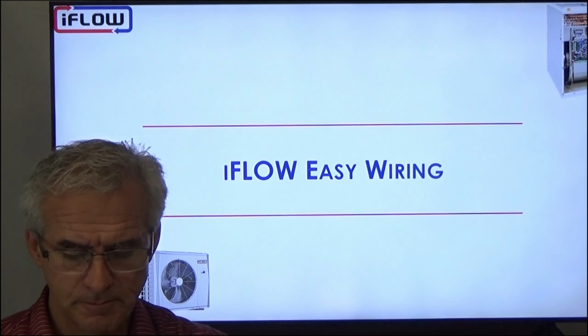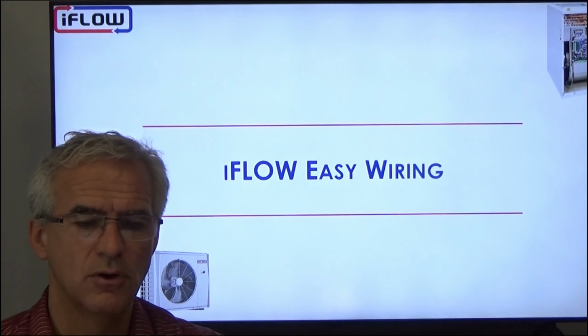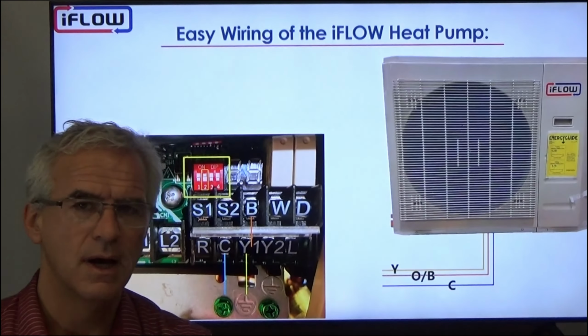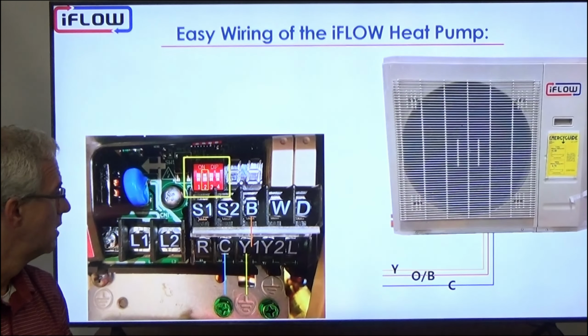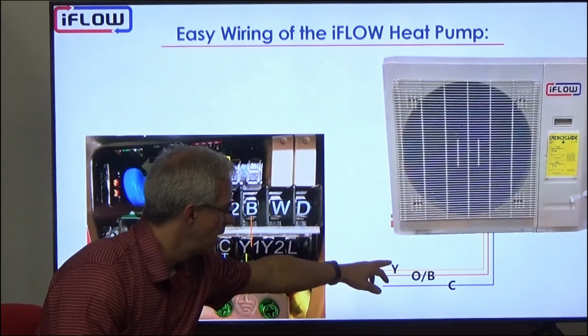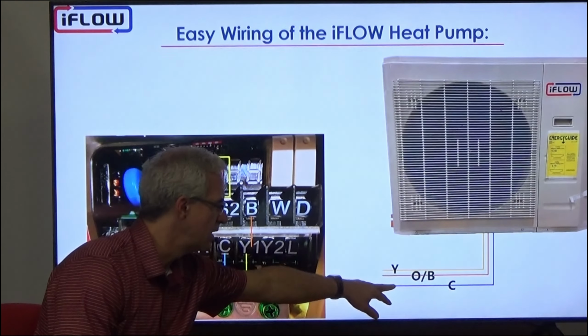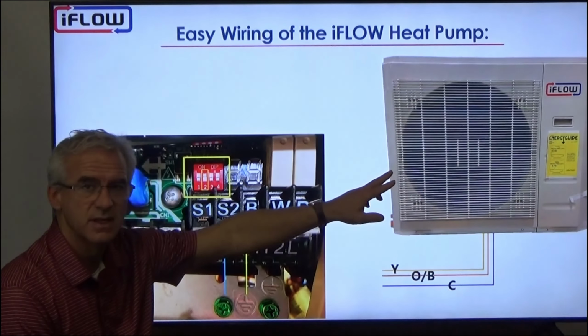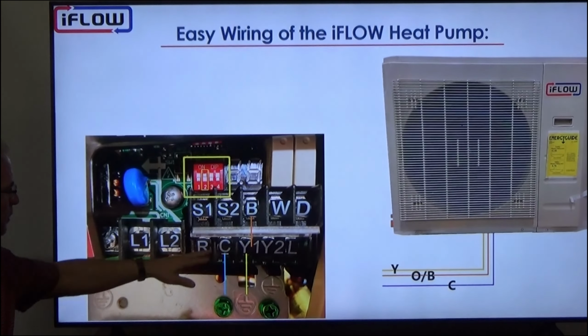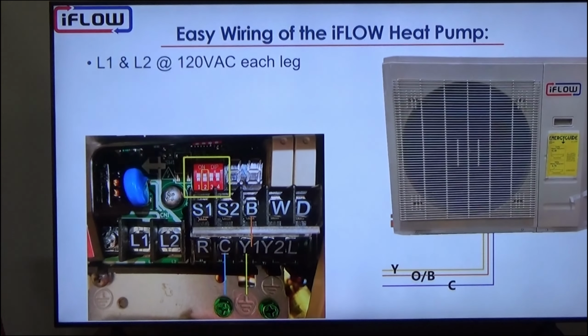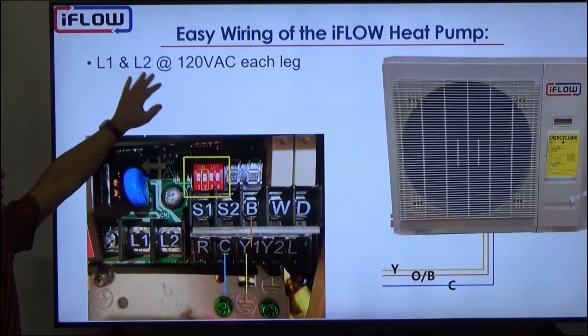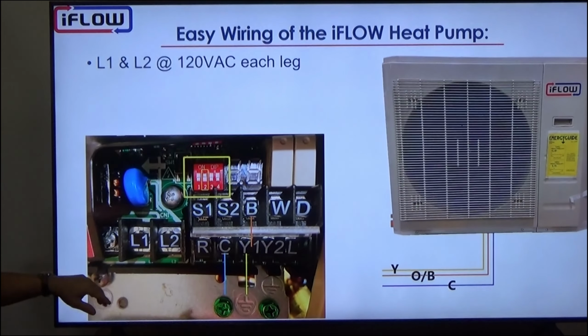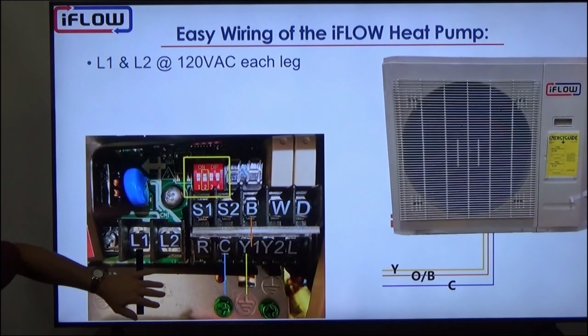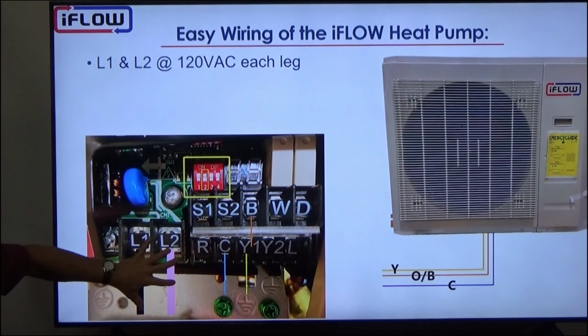In terms of wiring, the wiring to the iFLOW outdoor unit is very, very simple. We only require 3 wires. So we have a Y wire, an O or a B wire, and then a C wire. So 3 wires going out to the condenser unit. They connect simply to these contacts. So let's look at it. We have our main power. So we'll have L1 and L2, so leg 1 and leg 2, 120 volts each. They would come in, right, L1 and L2. So that's our main power, 120 volts each leg for 240.